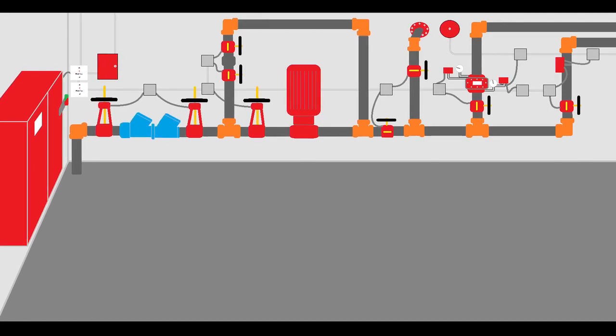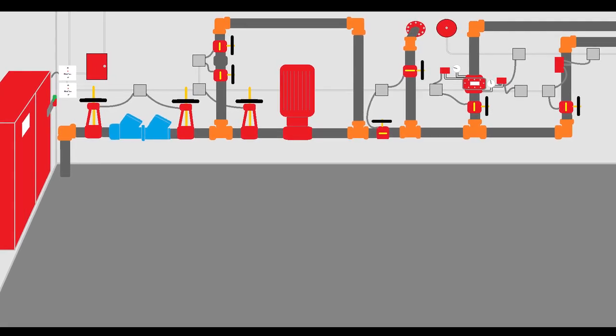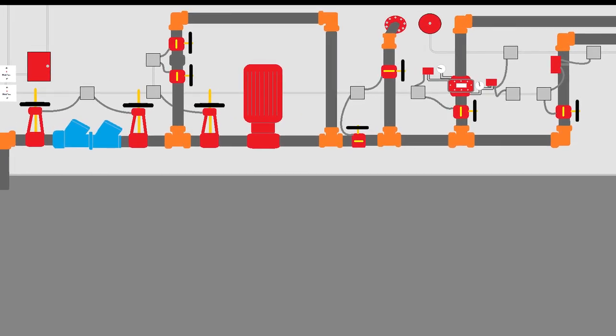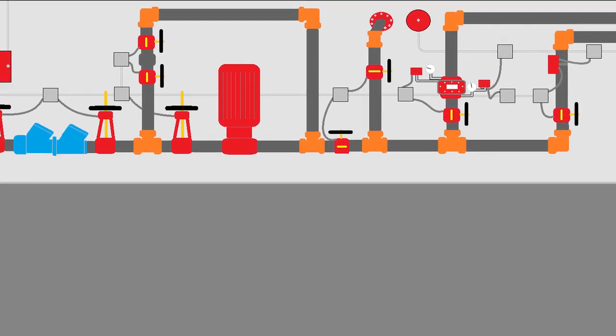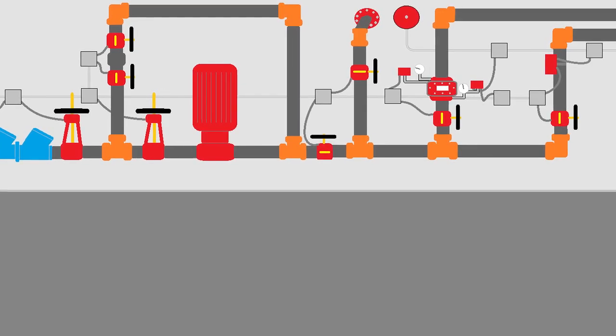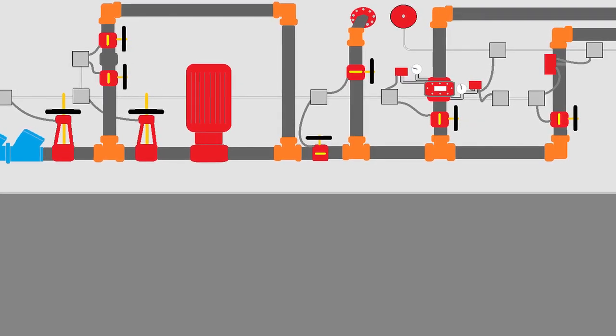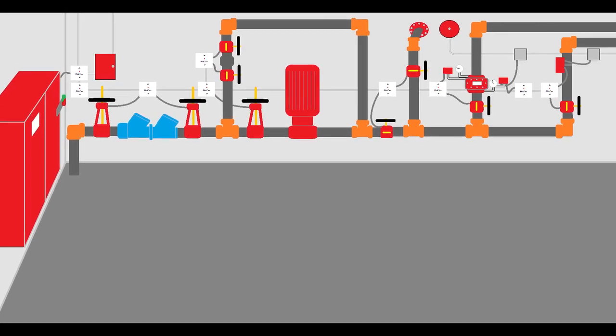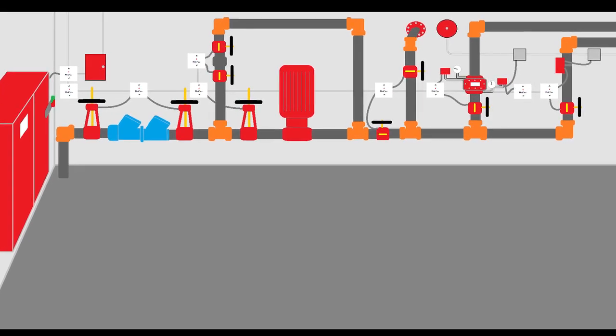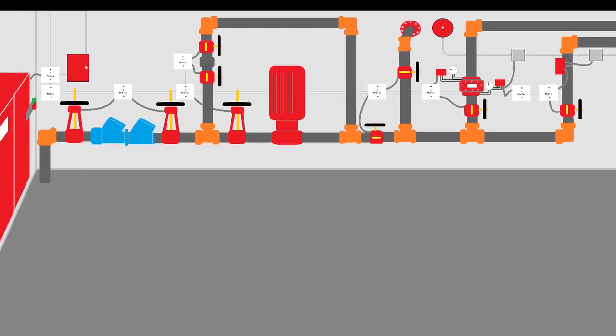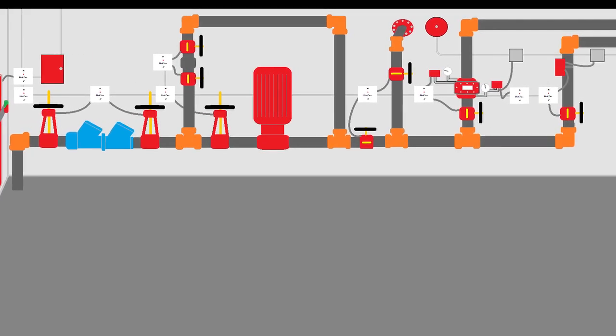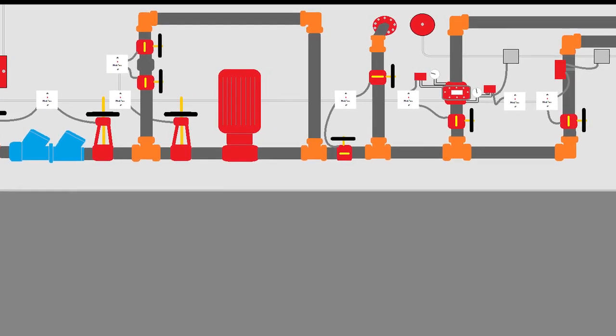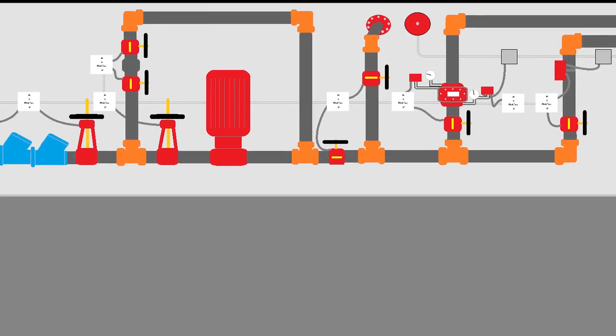I'd like to focus on how the different monitor modules we'll use here will connect to the various devices we need to monitor in the sprinkler room. In this room we have several different types of valves and devices that need to be monitored by the fire alarm panel. One option to monitor the devices in this room would have been to put either a single point or dual point monitor module by each device or each pair of devices as you see here. That would be a perfectly acceptable method of monitoring these devices and in most cases would probably be the preferred method.